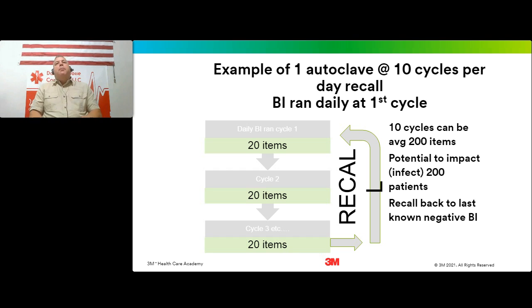I always like to put it in this perspective. If you were to run what's called every load monitoring, if you ran a BI on every cycle and the cycle you just pulled out of the autoclave fails, what does our literature tell us? We have to recall back to the last known negative BI, so that would only be the last preceding cycle. So you're lowering that window of risk, you're lowering that window of liability.